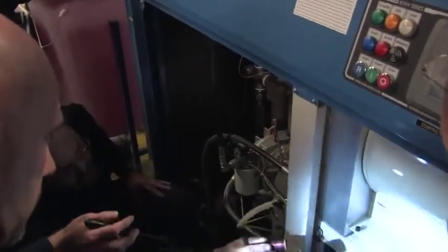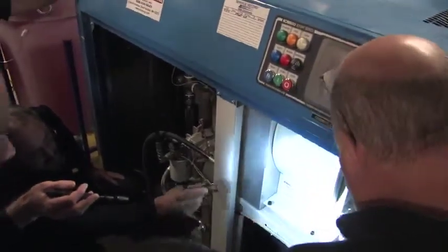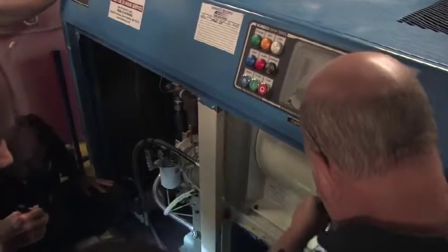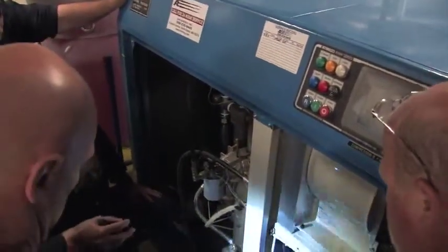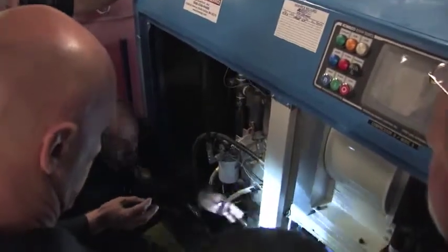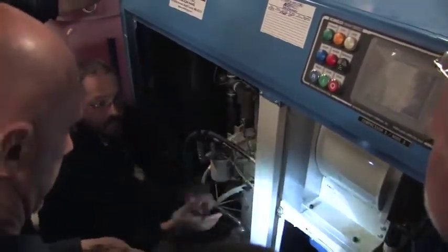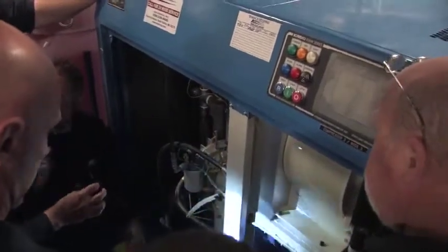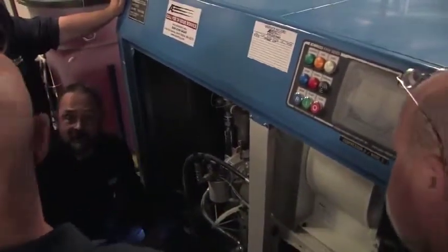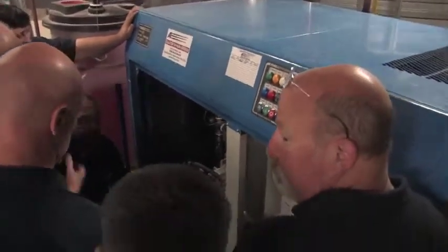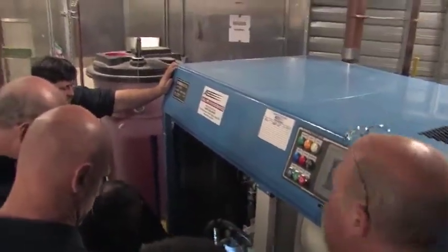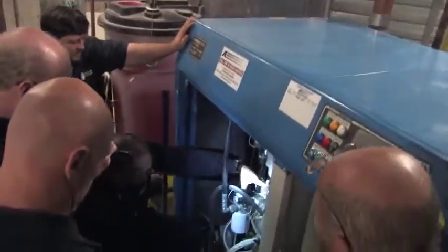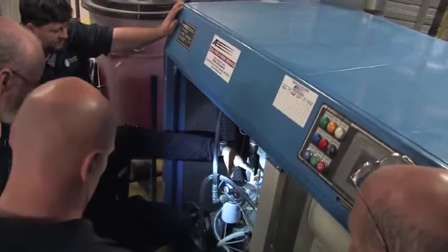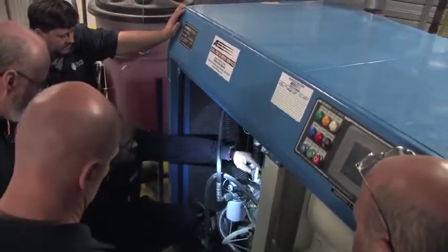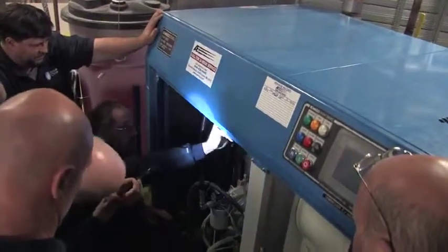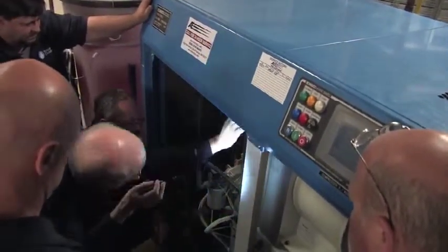You'll notice all your pressure transducers and sensors are right there in a row. And if you ever have to change a motor, this is a lot more accessible than when the electrical cabinet was here and the other cabinet was there, because the only way to get to it was from the backside. And if you look at the backside, you can see that it's not fun to take apart. These are made to access, the others are not. So you've got your inlet, you're going into the first stage air end, compressing to about 30 pounds. Out of this through a fin cooler, up into the top and into the intercooler, the first stage cooler.